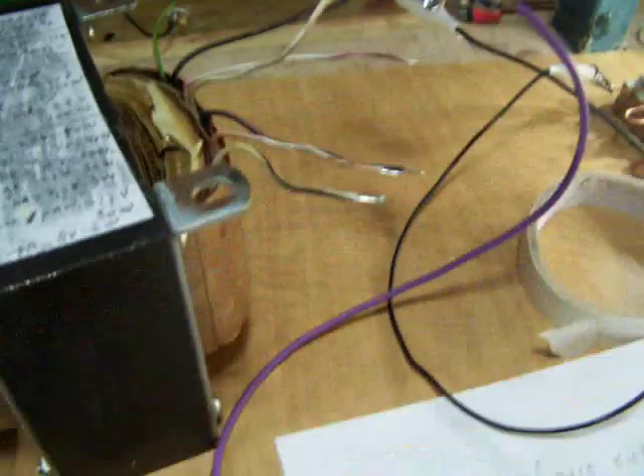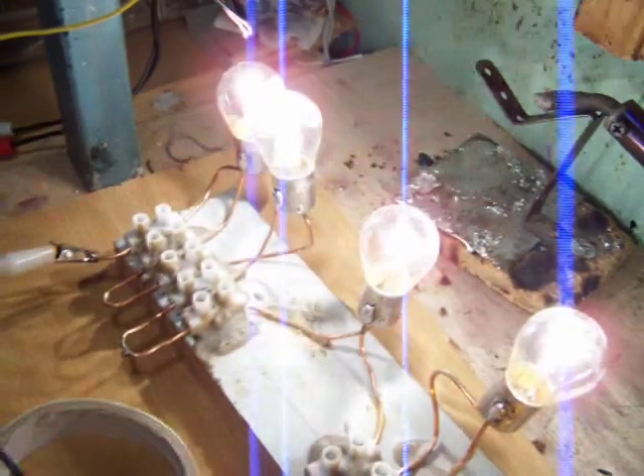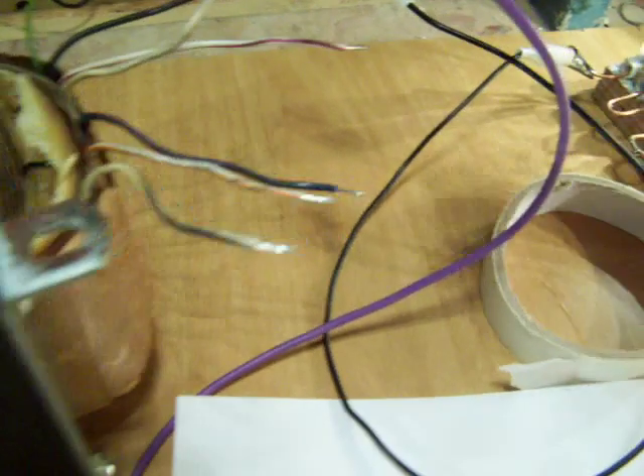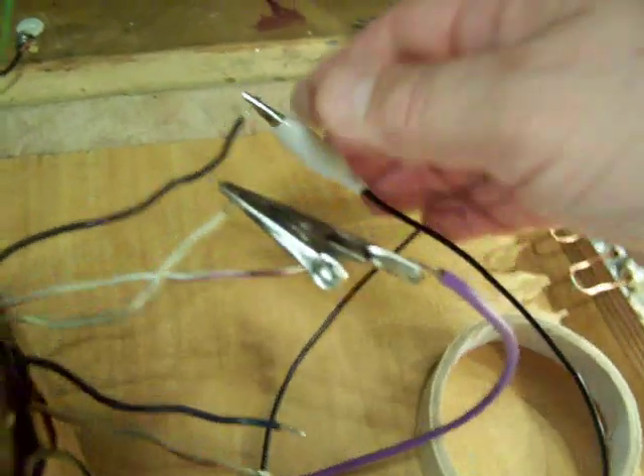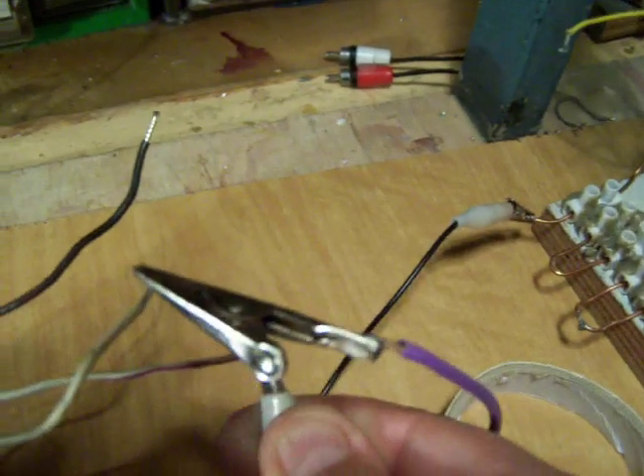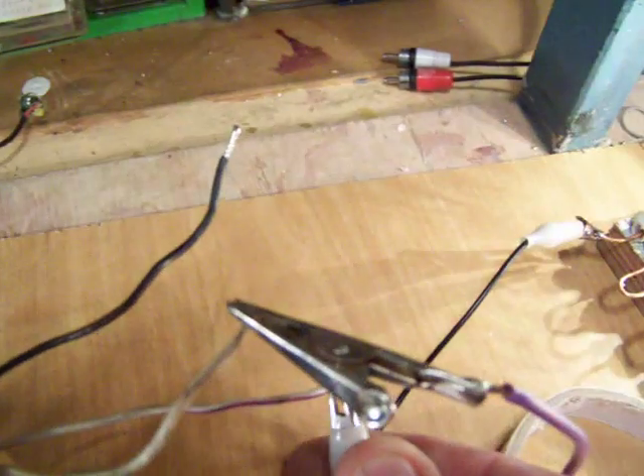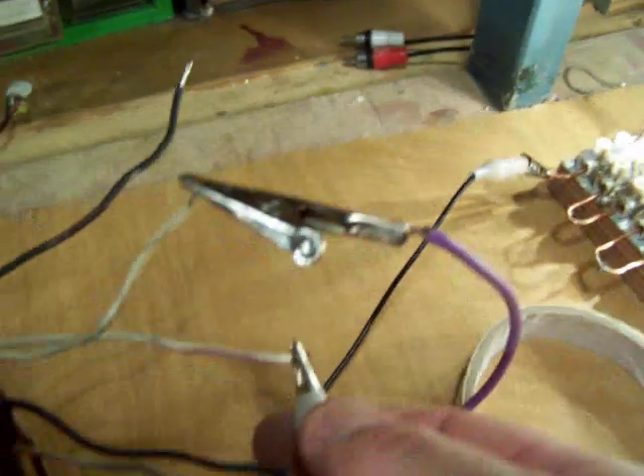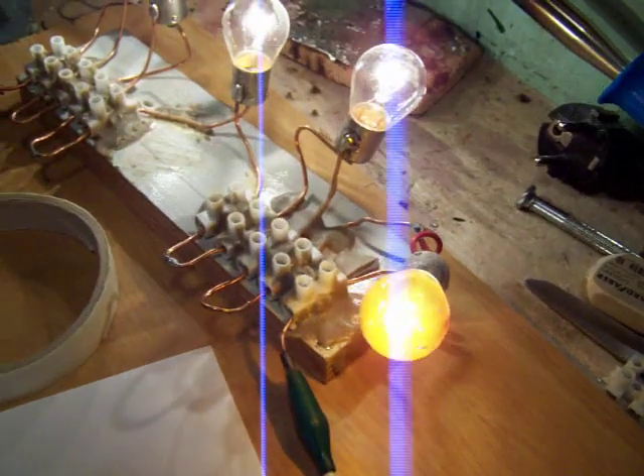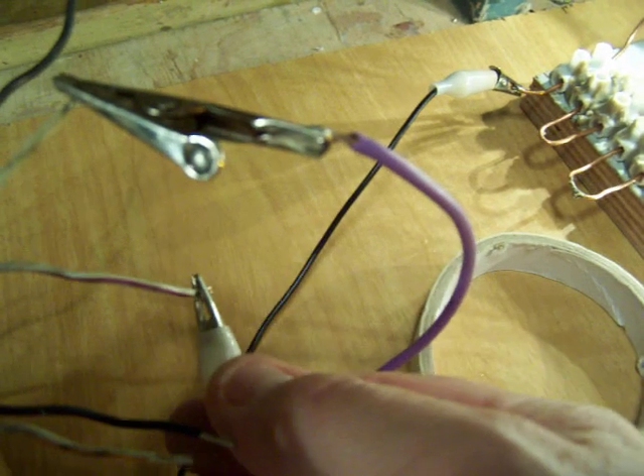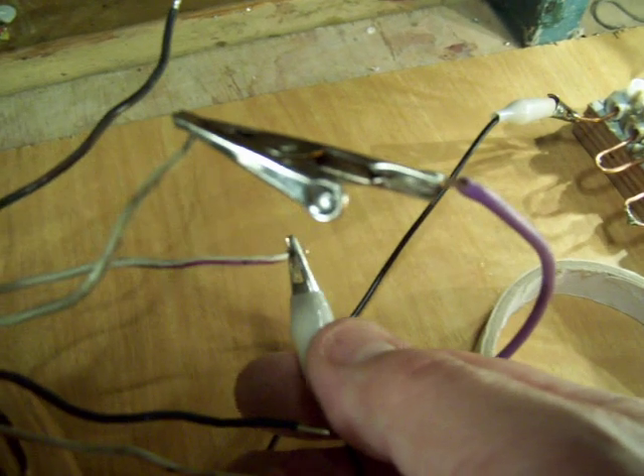Now you can use this lamp bank to test other windings. For instance, now I remove this connection and I go to this connection here. This is another winding from the transformer. Hope you can see it. All the lamps are lighting at the same power, so this means that this winding from the transformer has also the same power as the first winding.